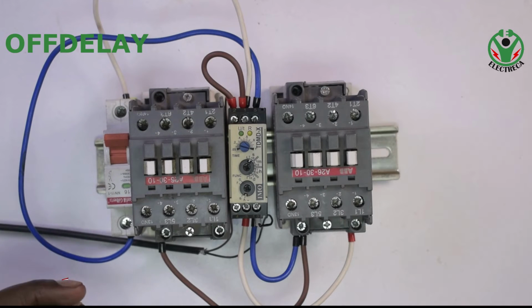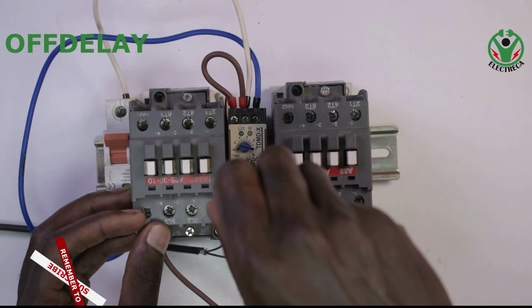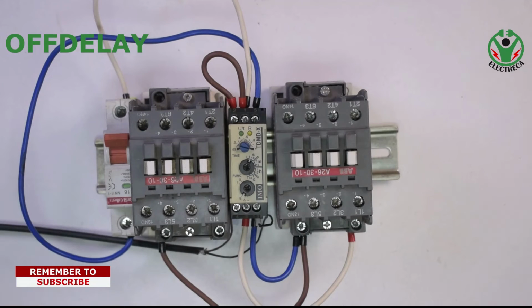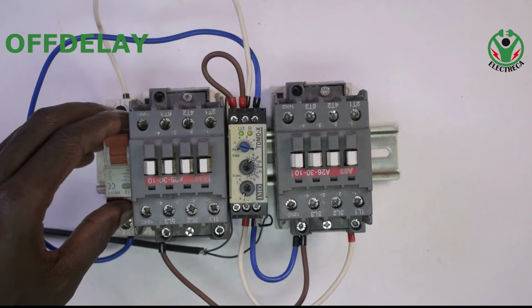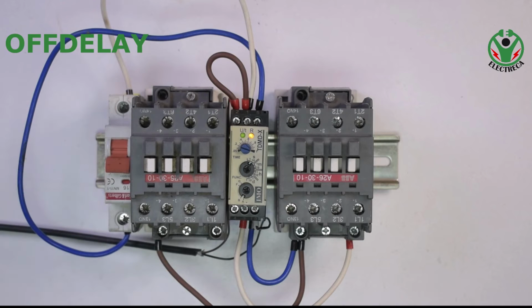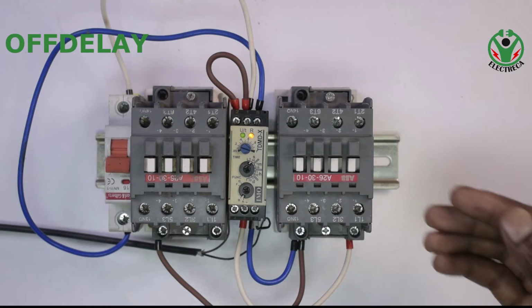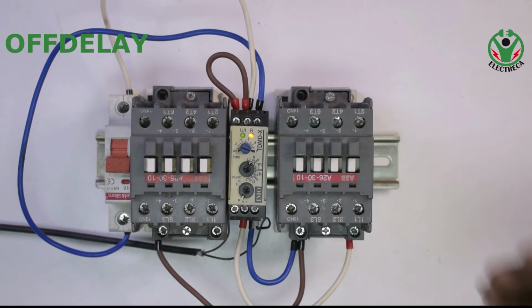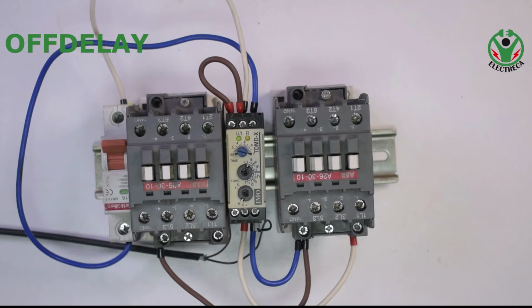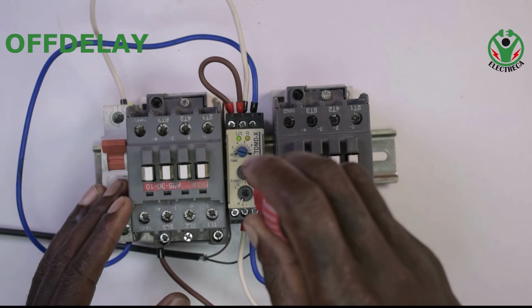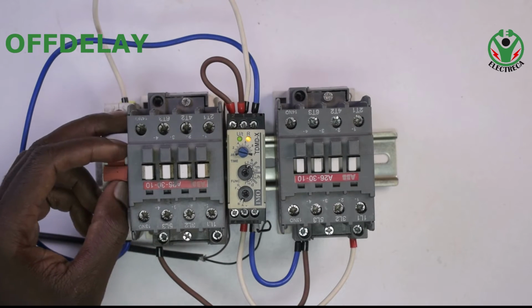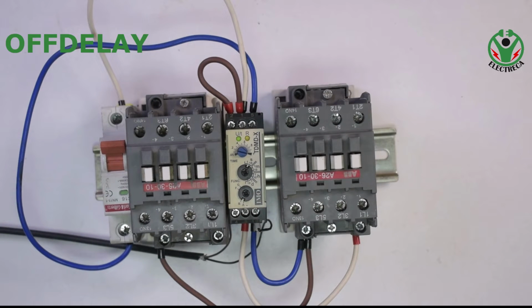Let us go to B. Make sure you change the dial. So we are at B. Now, let us switch on. We have a continuous supply on our timer, if you see. Now, the moment you close S, the contact will close and you see our contactor is in. But if you open S, the timer will start counting and it will switch off. If we increase just a little bit of time, you switch on, that is B. When you switch off, the timer will count and then the circuit will be de-energized.